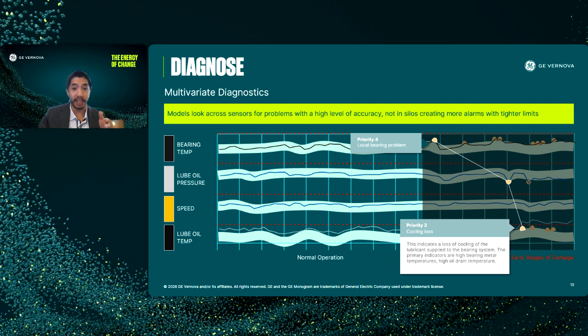In this case, you're seeing first in this timeline, left to right, a priority 4 local bearing problem. It's an early stage indicator, purely based on the bearing temperature, which is beginning to deviate. But right now it's isolated to just that sensor, so the system is flagging it as a priority 4, our lowest priority.